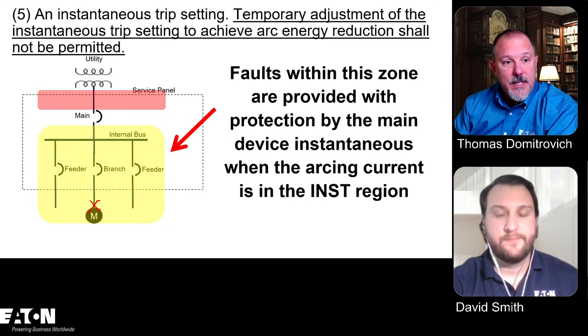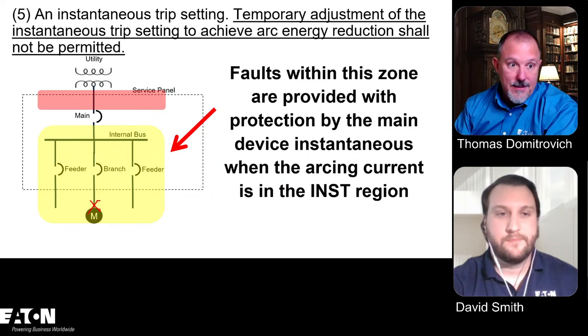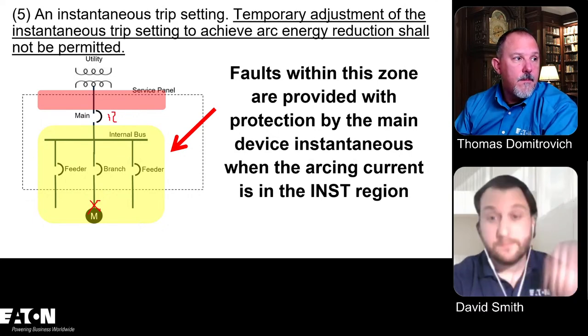Now, I thought 240.87 applied to all 1200 amp circuit breakers, even one that is downstream from another. Yes, that is exactly right. But if this is a 1200 amp breaker and this is 800 amp, I only need it on this breaker, not that breaker. If this guy's 2000 amps and that guy's 1200 amps, I have to put it on both breakers.